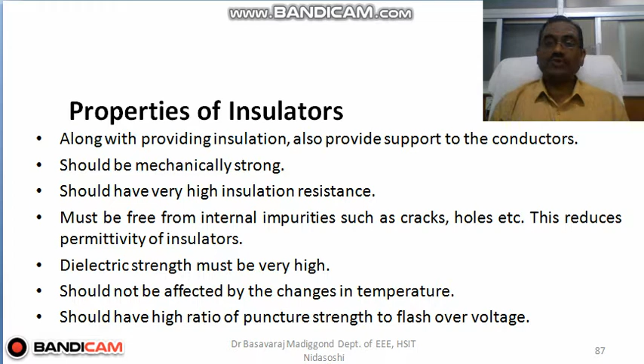They should have a high ratio of puncture strength to flashover voltage. If the voltage increases, there are chances that the insulator gets punctured. If the insulator gets punctured, then the conductor will directly come in contact with the tower. So it should not happen. Therefore, it should have a high ratio of puncture strength to flashover voltage.